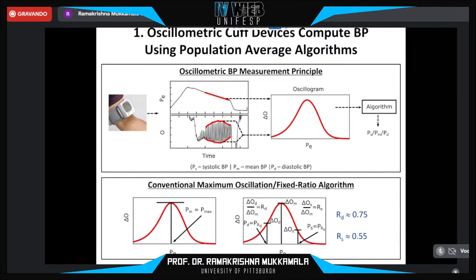The measured cuff pressure indicates the applied pressure and is superimposed with tiny oscillations representing the pulsatile blood volume in the artery. Since the arterial blood volume pressure relationship is nonlinear, the amplitude of the oscillations varies with the applied cuff pressure. Blood pressure is computed from the oscillation amplitude versus cuff pressure function, which I'll henceforth call the oscillogram.